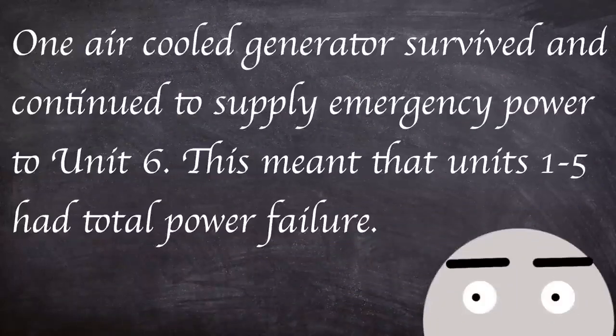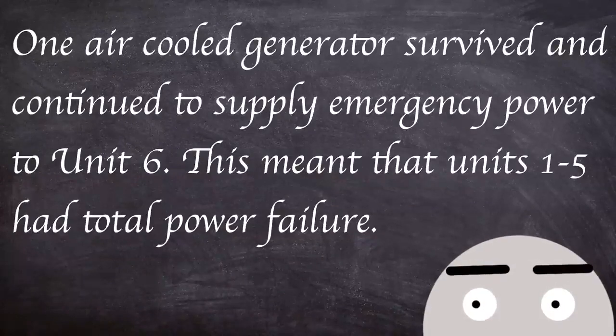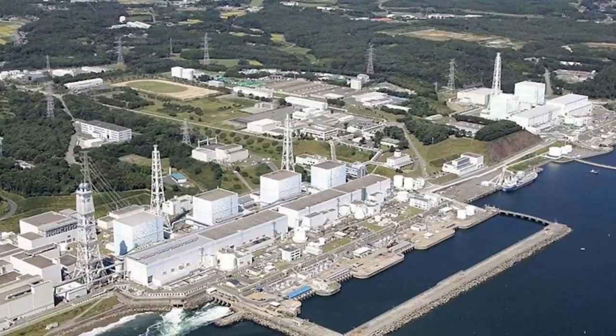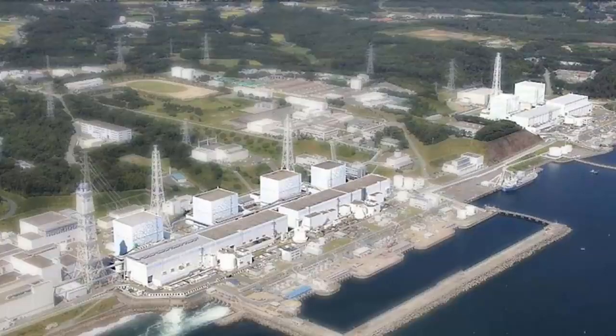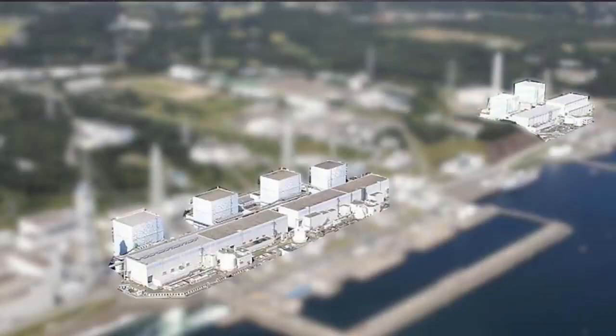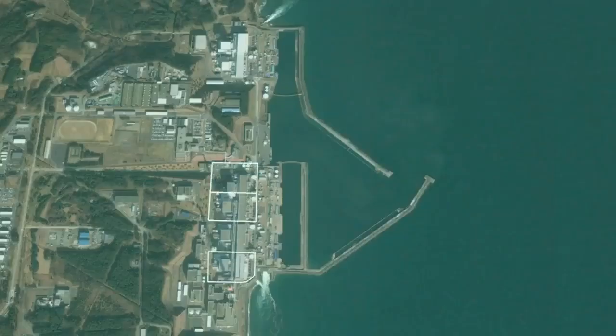One air cooled generator survived and continued to supply emergency power to unit six. This meant however that units one to five had total power failure. The power station was designed to be able to work off DC batteries for up to eight hours in the event of a loss of AC power generation. However, some of these systems were also affected by the flooding inundating the functional DC systems. Power started to dwindle in units one two and four 15 minutes post-flood due to loss of all AC and DC power.